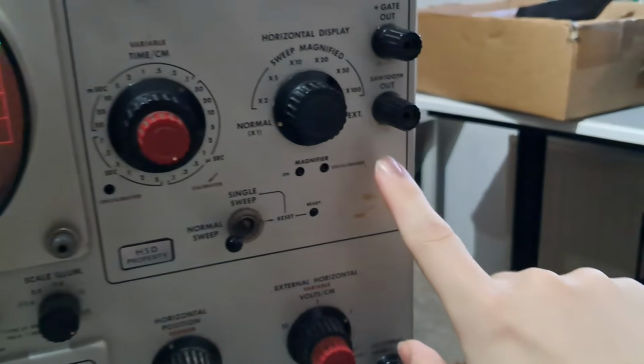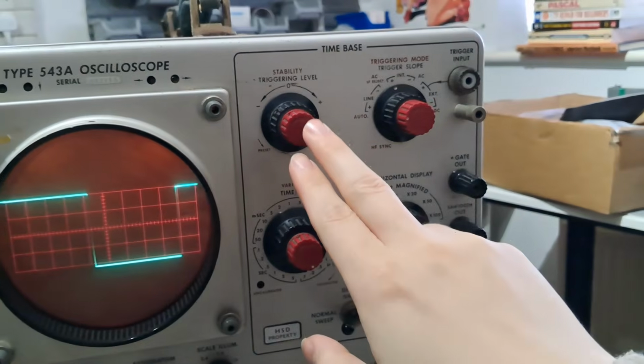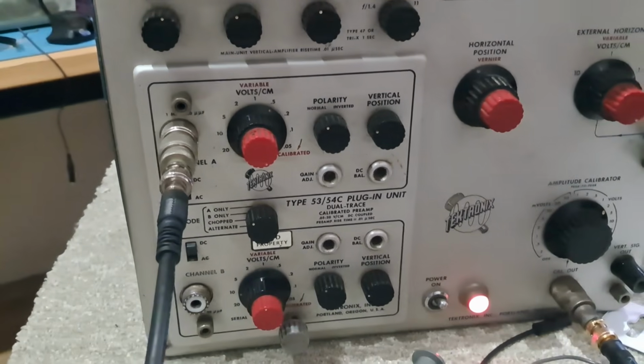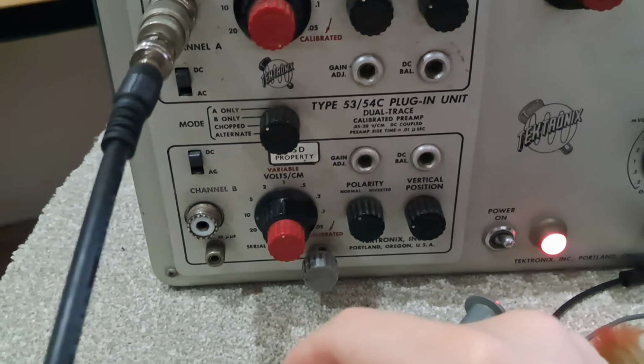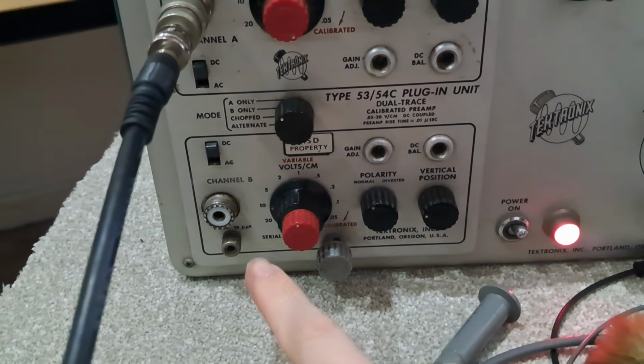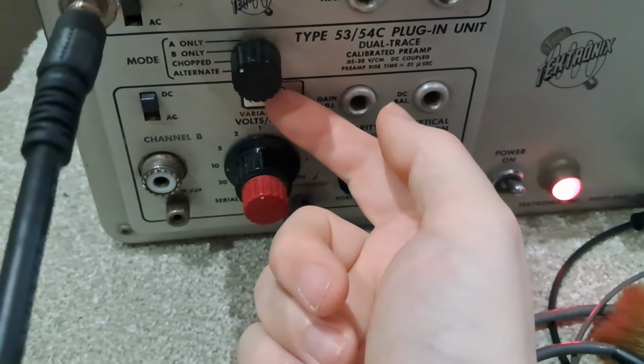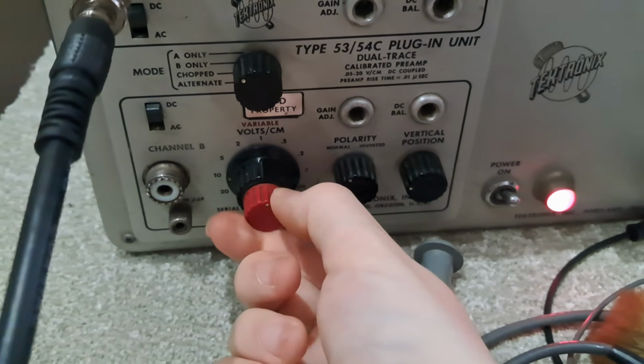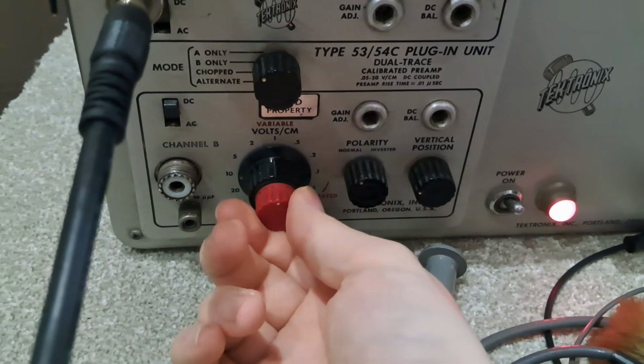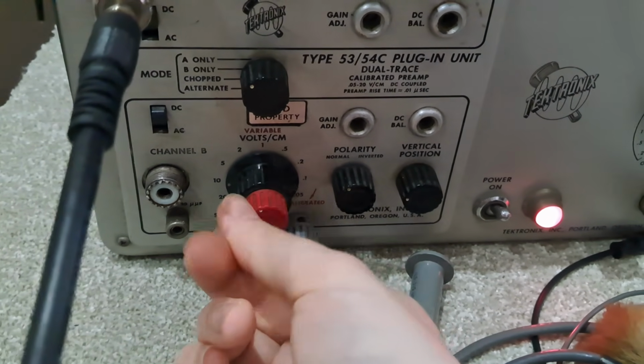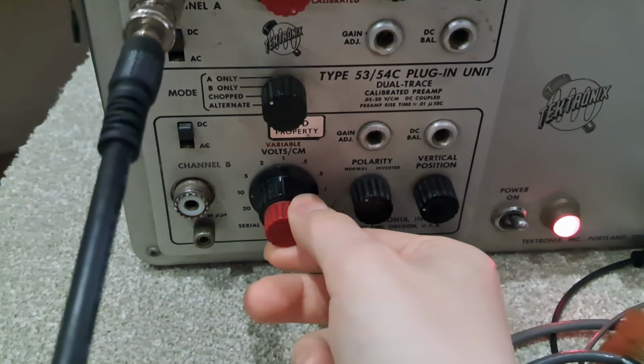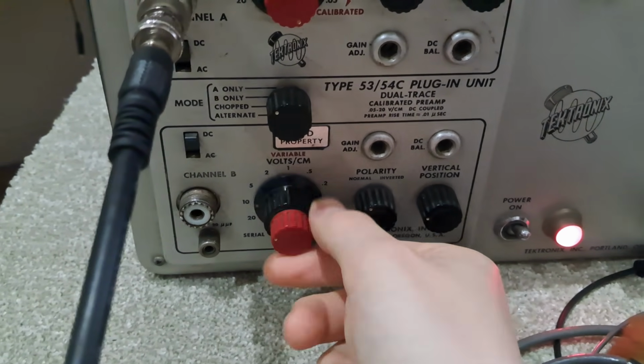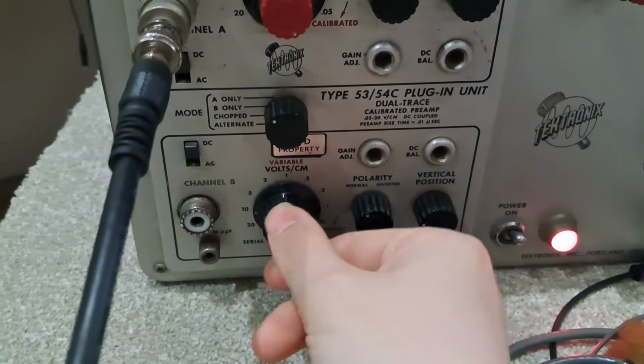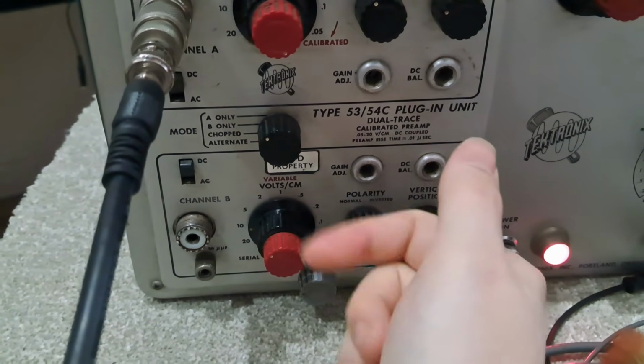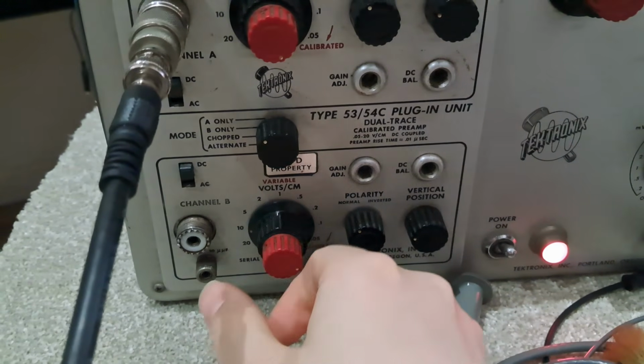And also the external horizontal input is working. Stability is working. Yeah, all the triggering modes. The only thing that isn't really working, at least not that well, is the channel B on this plugin. I think it's this red knob here, which is the variable to calibrate it. I think it might just need a bit of cleaning, but I think it could just be broken because I'm pretty sure it's not supposed to turn indefinitely. It's supposed to stop, and it isn't. So I think it actually is physically broken, the actual mechanism itself. So that might not be fixable, as long as one of the channels works, which it does.